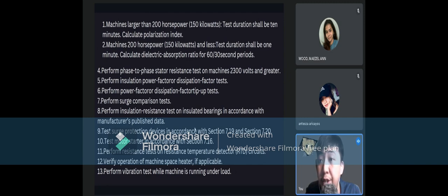3. Machines larger than 200 horsepower or 150 kilowatts: test duration shall be 10 minutes. Calculate the polarization index. 4. Machines 200 horsepower, 150 kilowatts and less: test duration shall be 1 minute. Calculate the dielectric absorption ratio for 60/30 second periods. 4. Perform phase-to-phase stator resistance tests on machines 2300 volts and greater.